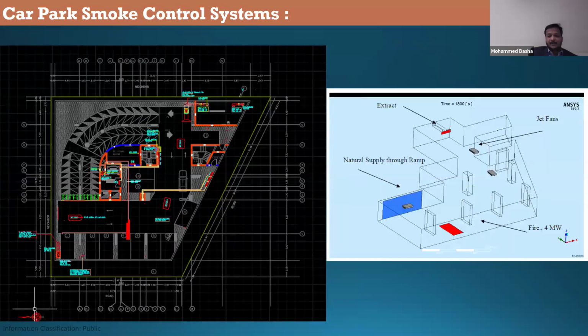So this is a simple one, I do not want to take more time. This is a simple CFD analysis, done in another software called ANSYS. You can do it in ANSYS also. PyroSim and ANSYS are both available to do it. So here, if you see, there are 3 jet fans at the top, 1, 2, 3, and this is the extract, and this is the fire location of 4 megawatts, a sprinkler-controlled car park. Fresh air is coming through the ramp.